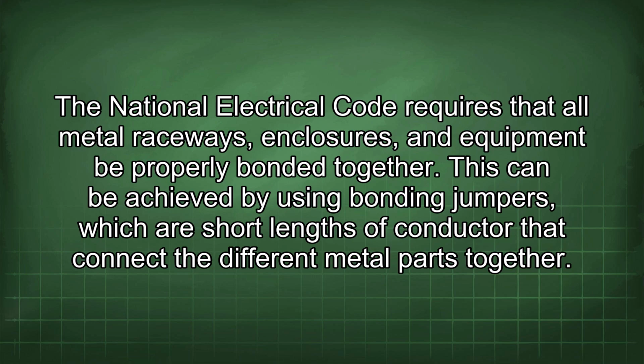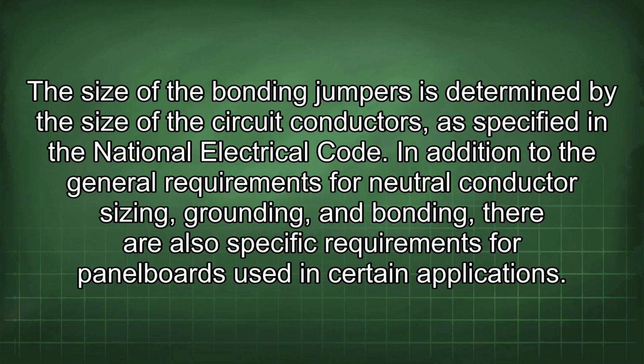This can be achieved by using bonding jumpers, which are short lengths of conductor that connect the different metal parts together. The size of the bonding jumpers is determined by the size of the circuit conductors, as specified in the National Electrical Code. In addition to the general requirements for neutral conductor sizing, grounding, and bonding, there are also specific requirements for panel boards used in certain applications.